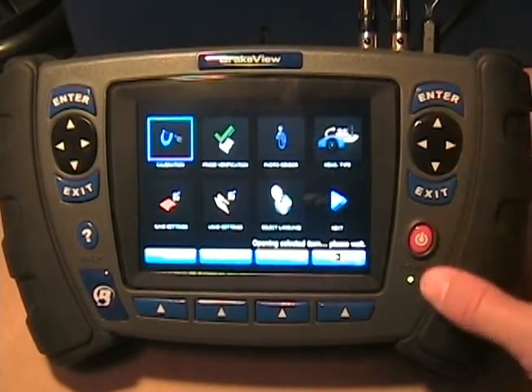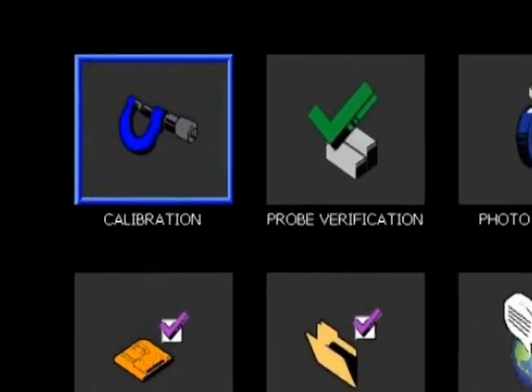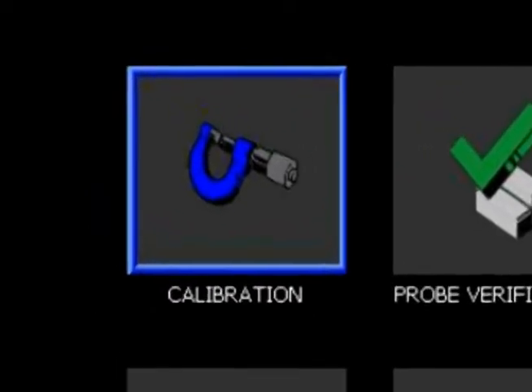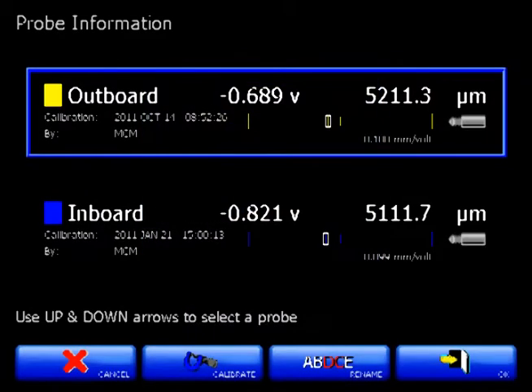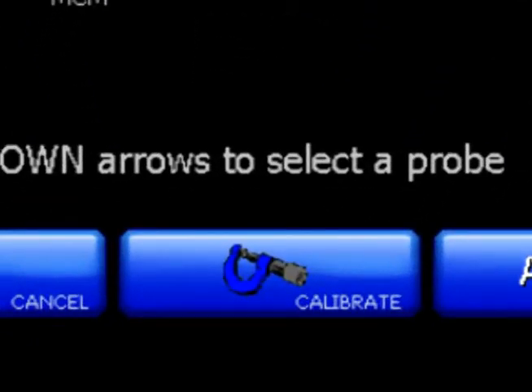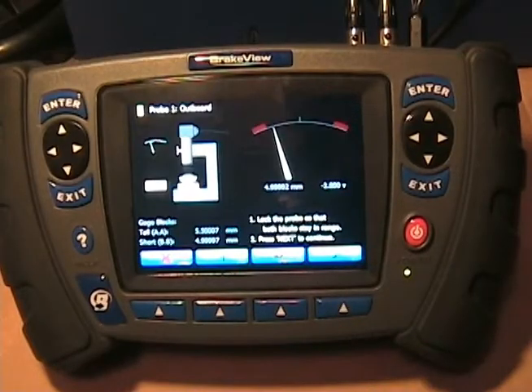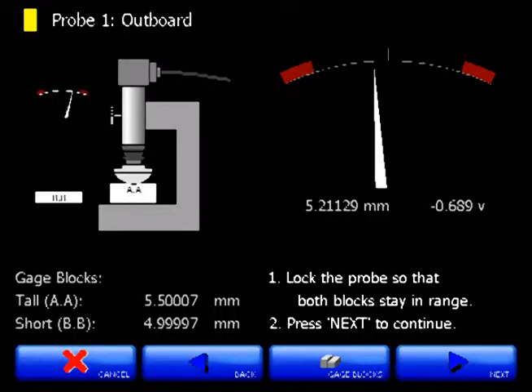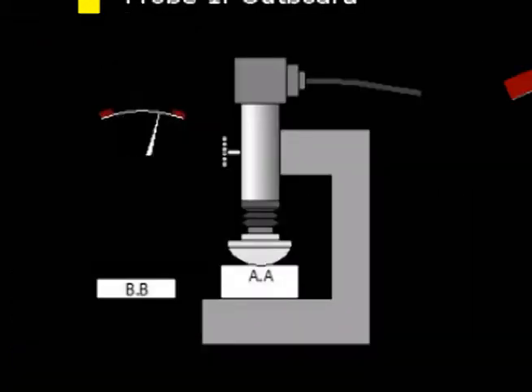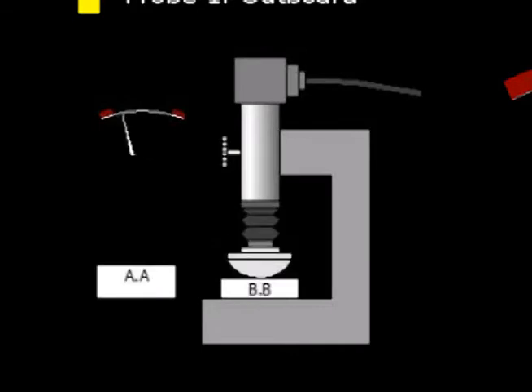let's take a look at the calibration process. To calibrate the BrakeView system, we're going to go to the calibration menu option and select it. When we do that, we'll be presented with the two probes for the system. The arrow keys will help us choose the yellow probe or the blue probe. In this case, let's choose the yellow probe, and we are now in the calibration setup screen. From the calibration setup screen, we can see a prompt that shows us a picture of two gauge blocks being swapped in and out of our fixture. That's what we're going to reproduce with the calibration fixture.